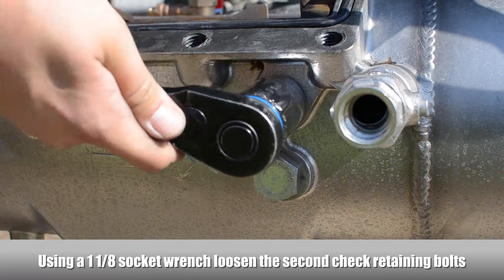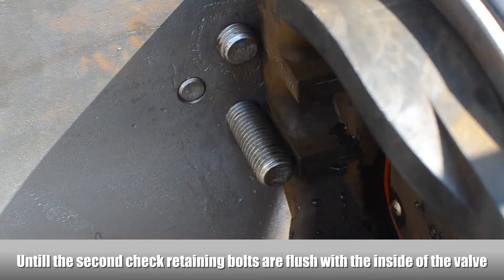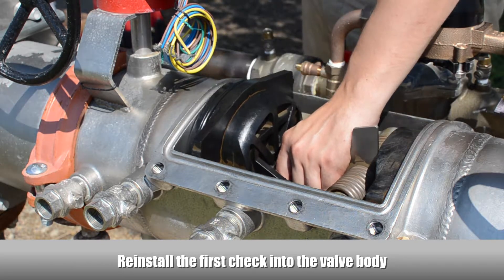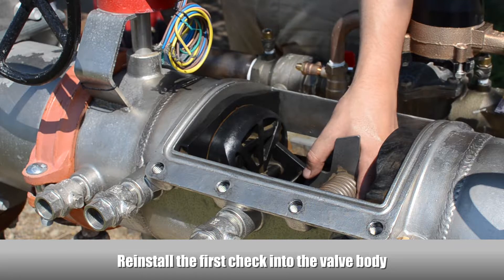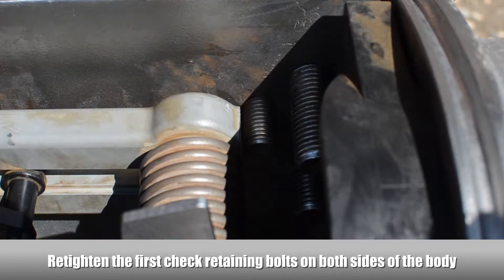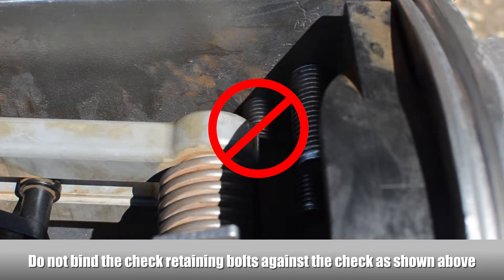To remove the second check, loosen the check retaining bolts located on both sides of the body until flush with the inside of the valve. Reinstall the first check into the valve body and make sure the o-ring seals properly against the surface. Re-tighten the first check retaining bolts on both sides of the body, making sure the retaining bolts don't bind against the check.